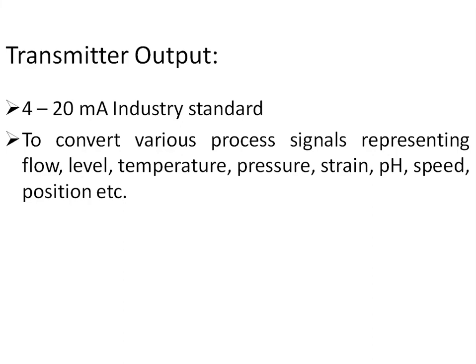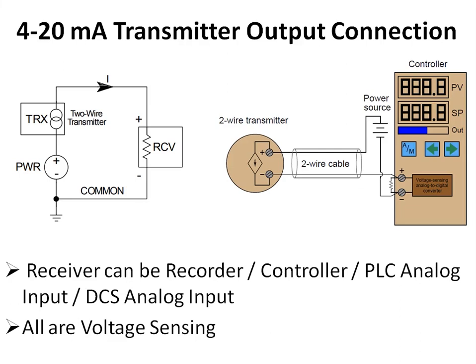The 4 to 20 milliampere transmitter output can be 2-wire, 3-wire, or 4-wire. The transmitted signal is ultimately received by a recorder, controller, or analog input of a PLC or DCS. As seen in the controller figure, the 4 to 20 milliampere signal is converted to a voltage using a resistor, because controllers, recorders, and analog inputs are all voltage-sensing devices.